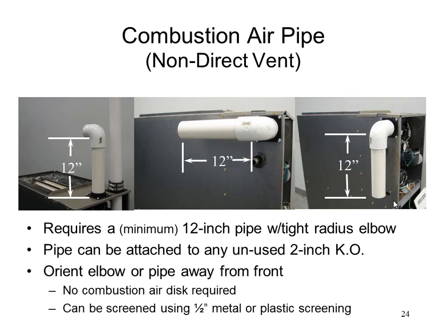If you need to, you can vent this furnace in what we'd call a single pipe installation, where I do not have an intake pipe. I just have the exhaust pipe. This is obviously not the preferred scenario. As you guys know from sealed combustion appliances of different types, it's always better to have intake air come from the outdoors as opposed to the indoors for multiple reasons. With one of the main reasons being, if I take the intake air from indoors, where's it really coming from? It's got to come from the outside at some point. So if I steal it from your house, I put your house into a negative, and your house has to make up that negative pressure.